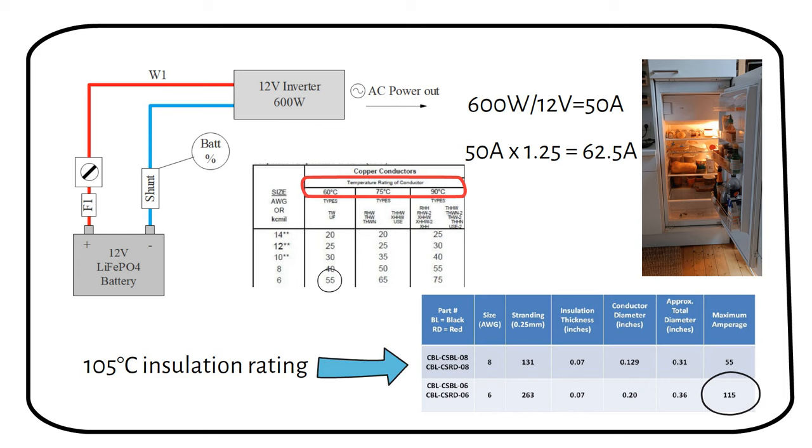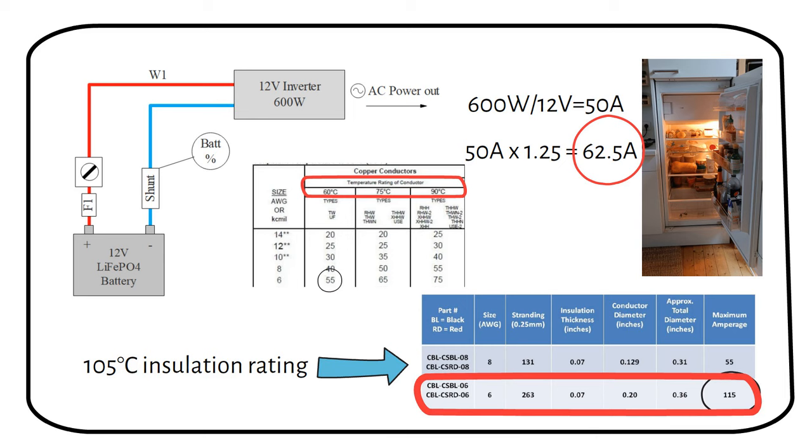Do you remember that we needed to use a wire rated at a minimum of 62.5 amps? We can see that we can use a 6 gauge cable because 62.5 amps is smaller than the maximum allowable current of 115 amps. An 8 gauge cable will be too small because it can only carry 55 amps. And that's how easy it is to size a wire.